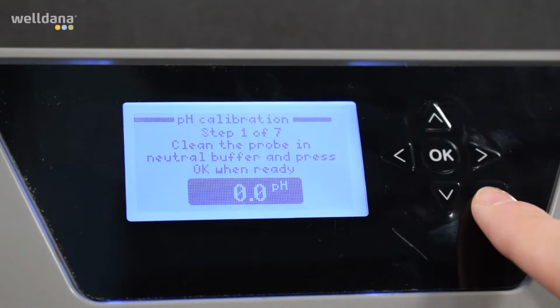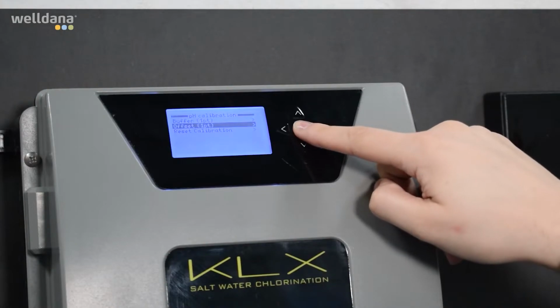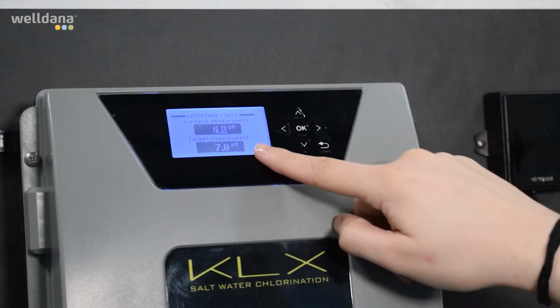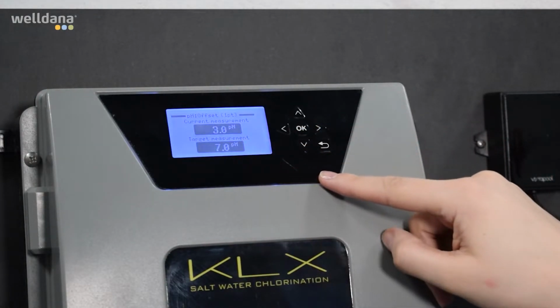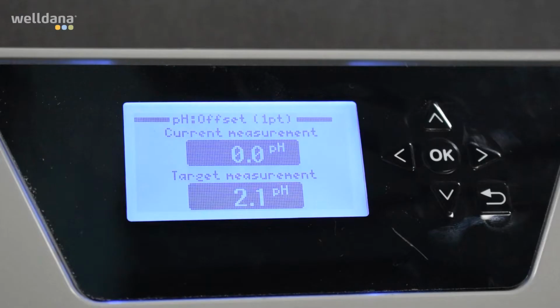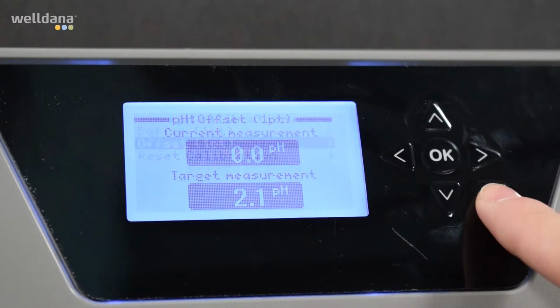Press the back button and select Offset. Here you can calibrate without using buffer solutions. This is only recommended for small deviations when you do a manual pH water test.